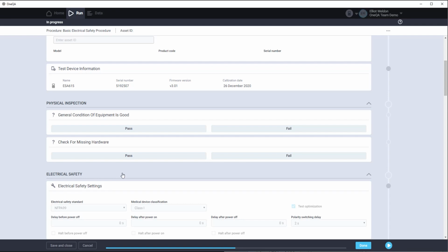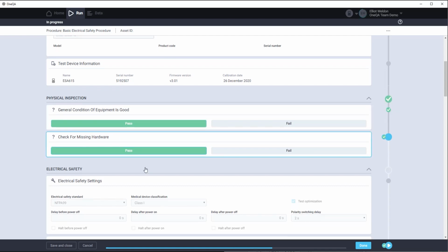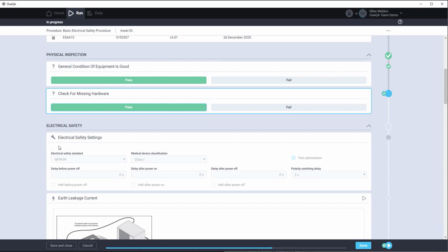One of the myths in the biomed world is that electrical safety can be skipped, but what you're going to see here is that using OneQA, there's really no reason to skip it. I mean, we're going to save a lot of time. We're going to run this test in 15, 20 seconds. So we'll start off with the physical inspection. Pass, pass. We'll use our NFPA 99 electrical safety standards.